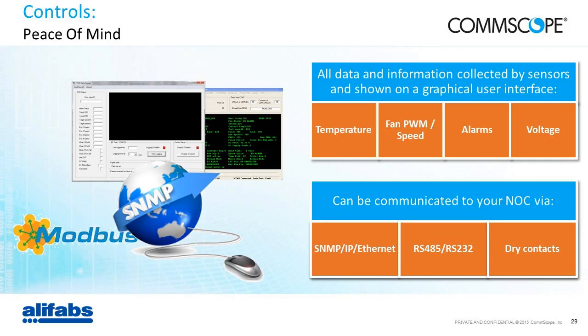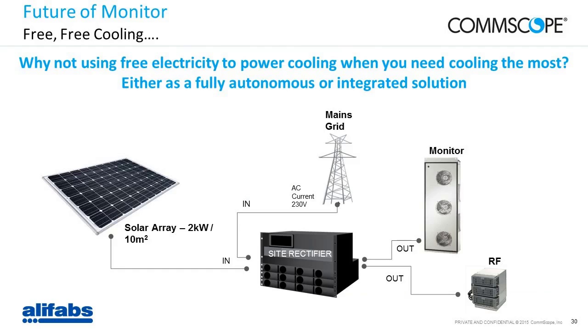Finally, I'd like to finish with something looking more into the future, because all of what I've been talking about is what we can currently deliver in pretty short lead times. But really what we're looking at today is a system that's completely autonomous. We've done quite a lot of sites where we've been refurbishing ceilings and rooftops of shelters. By doing that, we realized we are using available space to have a solar array. That solar array in the middle of the summer can deliver enough power for the monitor system, typically up to a kilowatt.